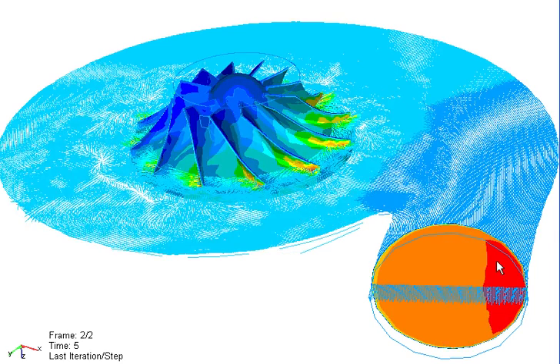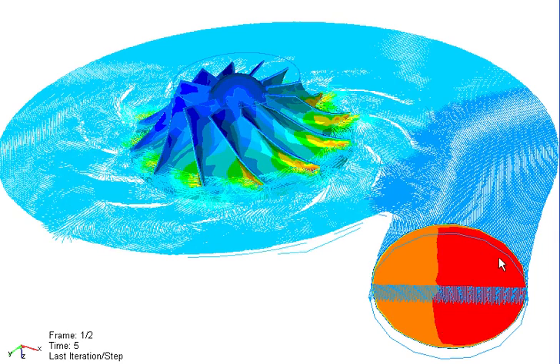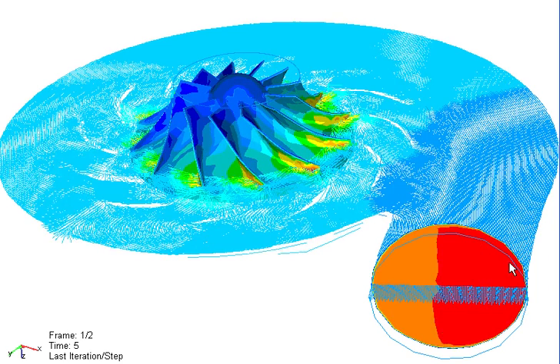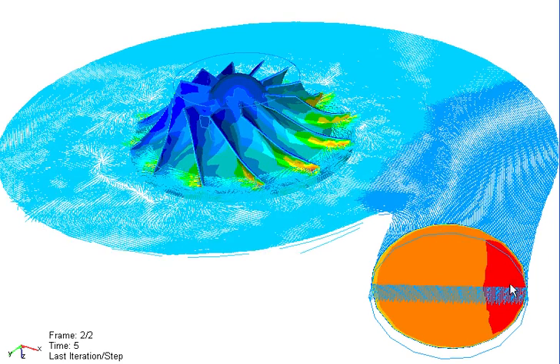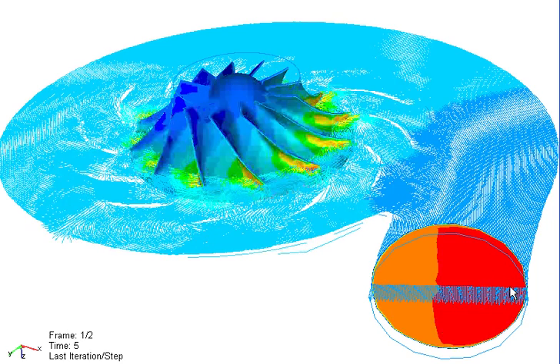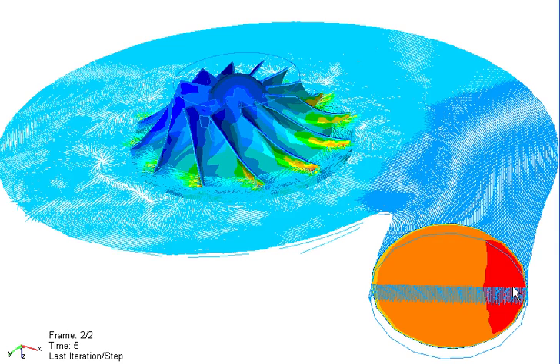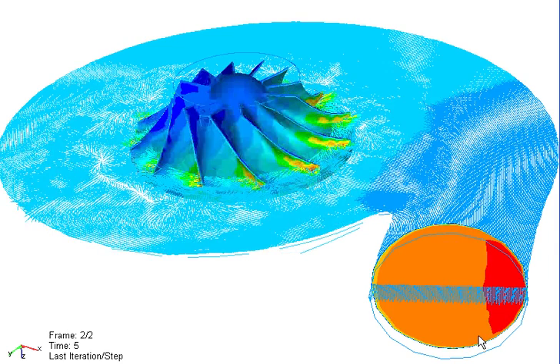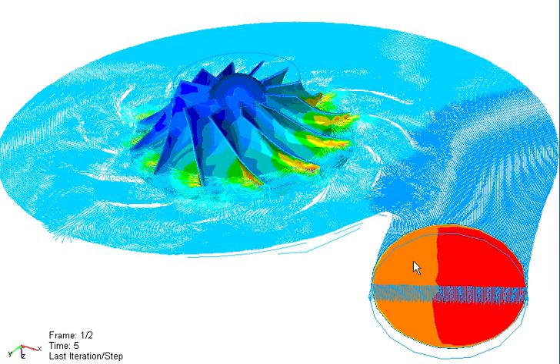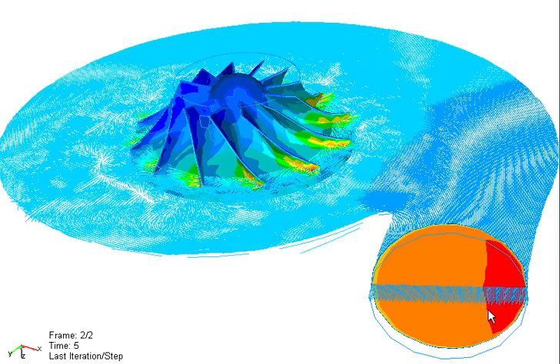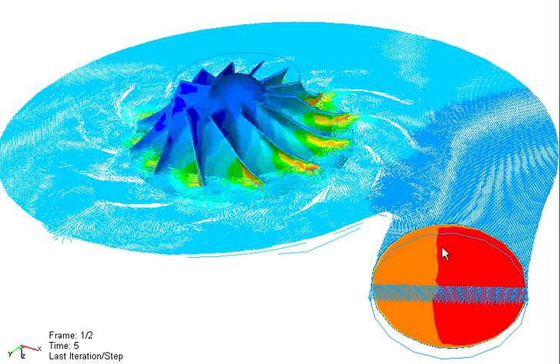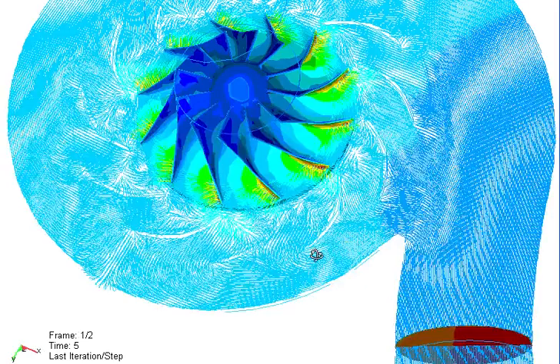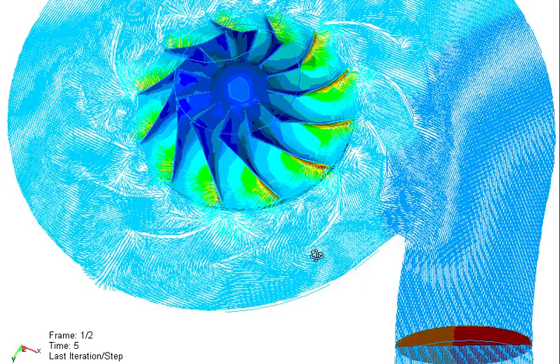You can see in one, the outlet of this volute - screaming velocity here at the side - not balanced at all. These guys needed to have more of a balanced outlet. So you can see the other one is more balanced, and here's the reason why.